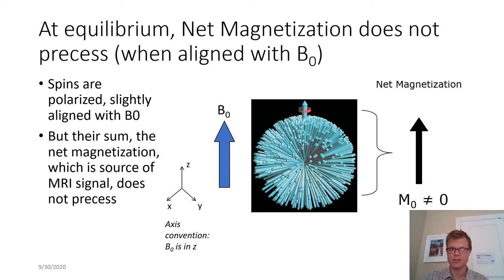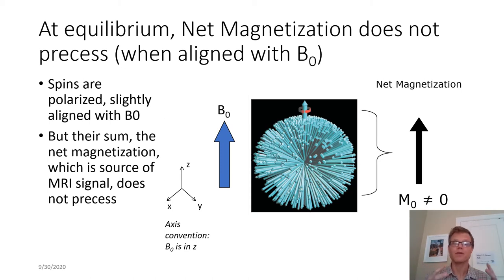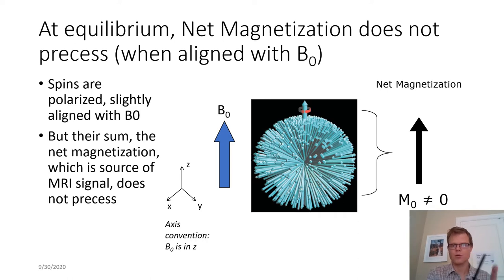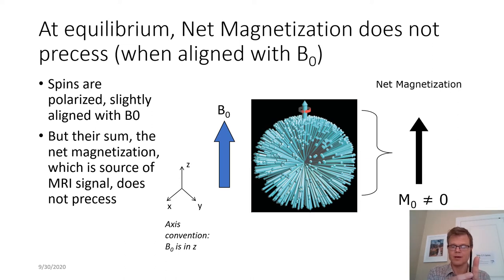I also showed in the previous lecture that at equilibrium, the net magnetization actually does not precess. The subject goes into the magnet, the spins become slightly preferentially aligned with B0, giving us a slight net magnetization pointed along the direction of B0. When B0 and the net magnetization are pointed together, the net magnetization cannot rotate around it — it's pointed in the same direction. It's only when the net magnetization is deflected somewhat from the B0 field that it will begin to precess. That's the fundamental problem that RF pulses are going to address.